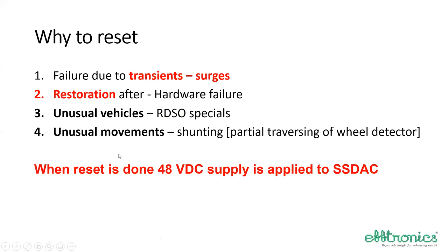Reset. Why does reset have to be done? There are different reasons. Number one, transients. Many times these surges won't cause permanent failure. They just cause a momentary failure and then the system comes back. But because it is a fail-safe system, what happened during those microseconds or milliseconds is not known, so the system will not be available for usage.